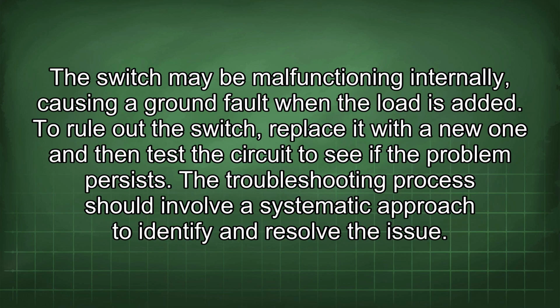Sixthly, a faulty switch could be the reason for the GFCI to trip. The switch may be malfunctioning internally, causing a ground fault when the load is added. To rule out the switch, replace it with a new one and then test the circuit to see if the problem persists. The troubleshooting process should involve a systematic approach to identify and resolve the issue.